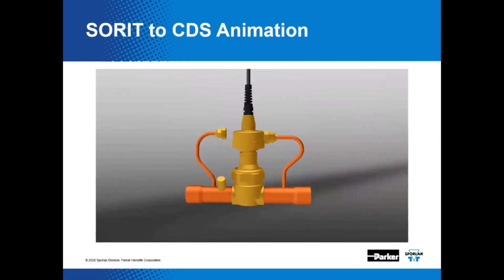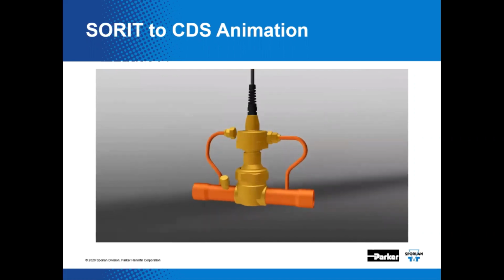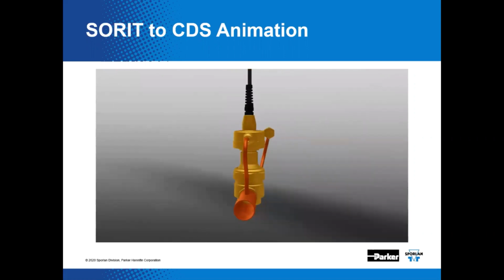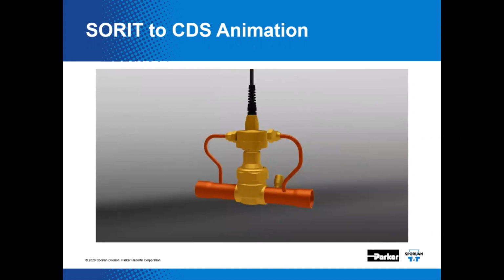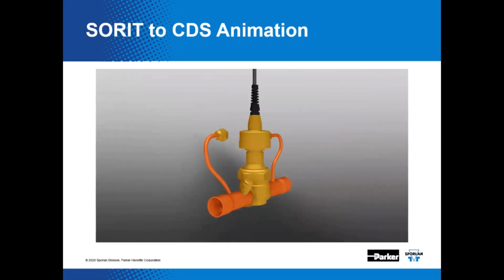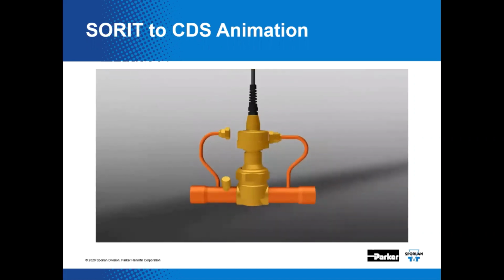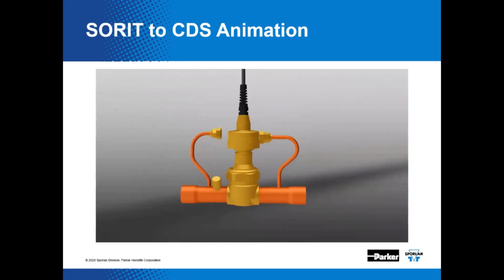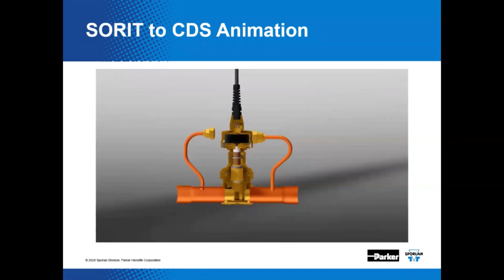We've got a parts kit that'll let you convert a SORIT valve to a CDS valve. Mm-hmm. And as you'll notice there, those pilot lines were blocked off and plugged in order to seal them. We do that when we're in the lab for the sake of sealing that. Out in the field, you could clip those flare nuts off and braze them closed, but we like to have access to it so we can change things around when we're doing tests.